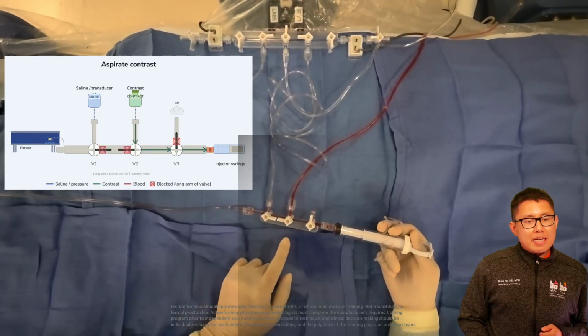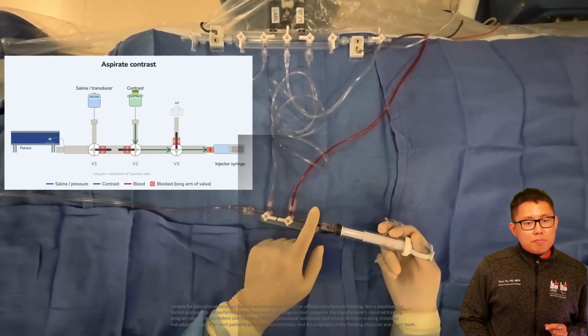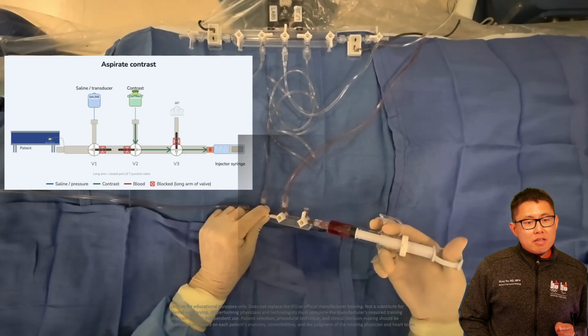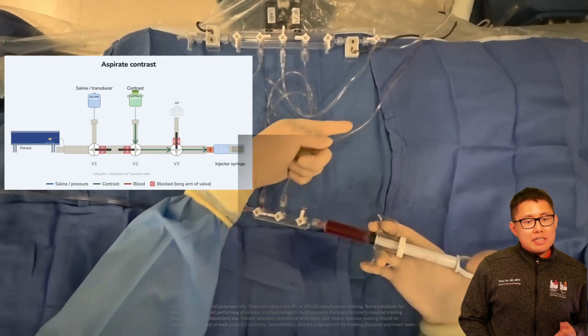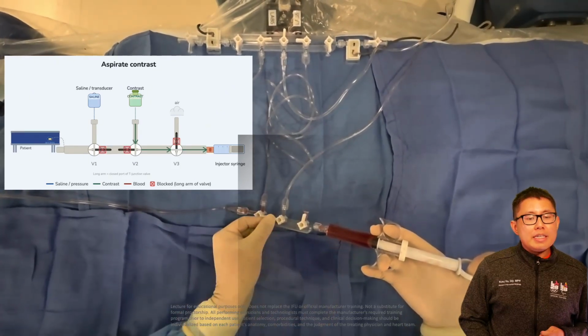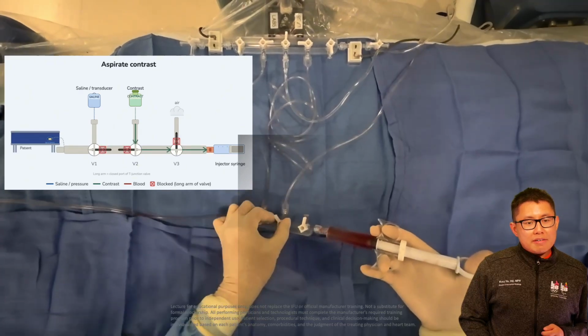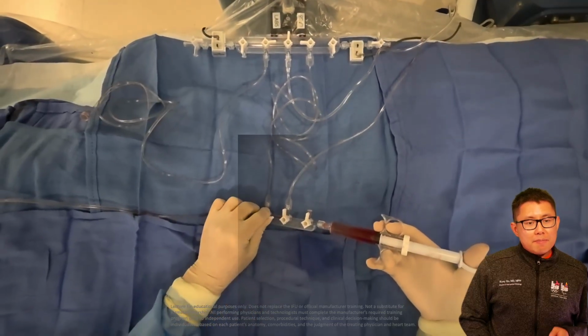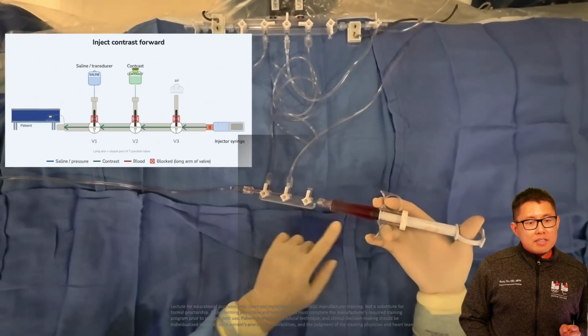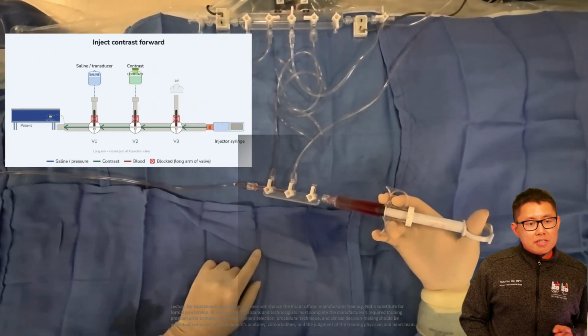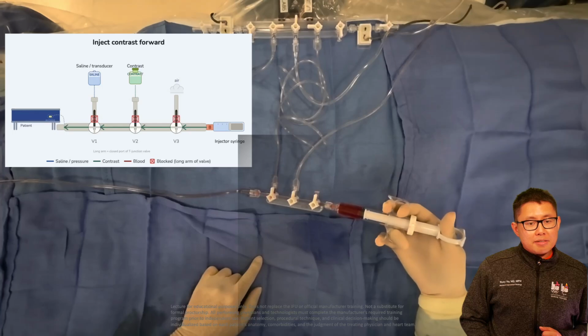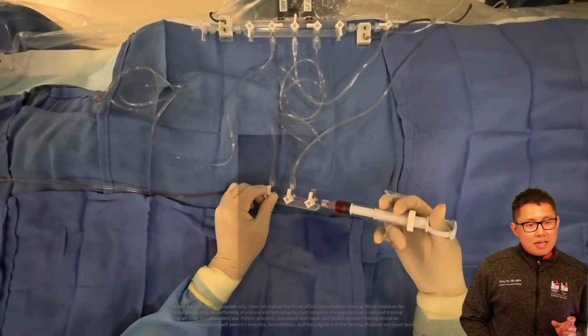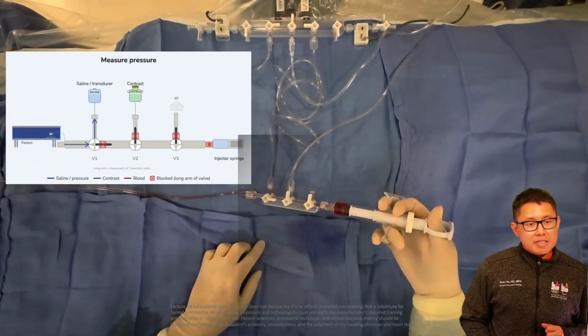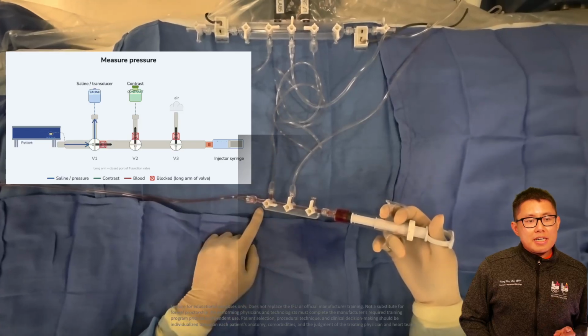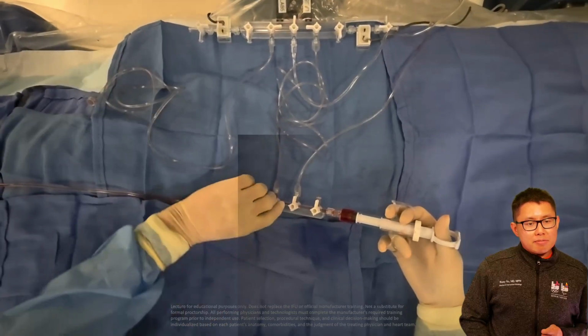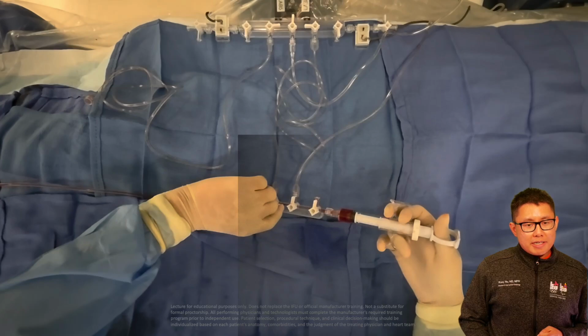Now let's say we want to aspirate contrast. We'll turn V2 pointing to the left, make sure that V3 is closed to air by pointing up, and then we can suck the contrast from the contrast reservoir into our syringe. When you have sufficient contrast, we can turn V2 back off to the contrast reservoir, turn V1 off to the pressure transducer. Now we have a direct connection to that long line to the patient, and we can inject as long as we have made sure that there's a safe pressure before doing that. The moment you finish injecting, we turn it back to measure pressure, which is V1 pointing to the right.